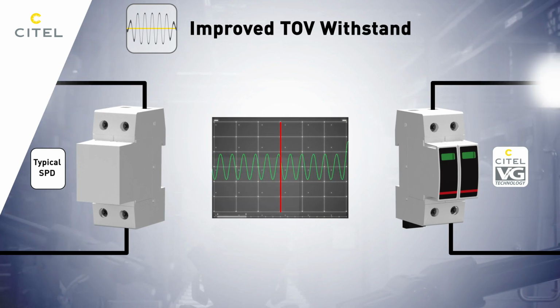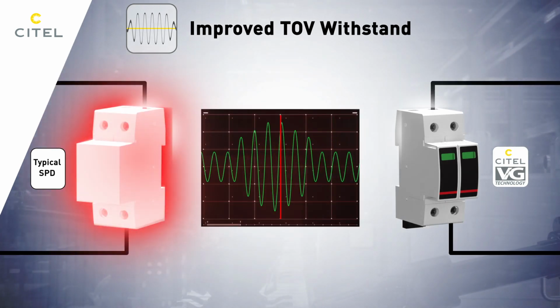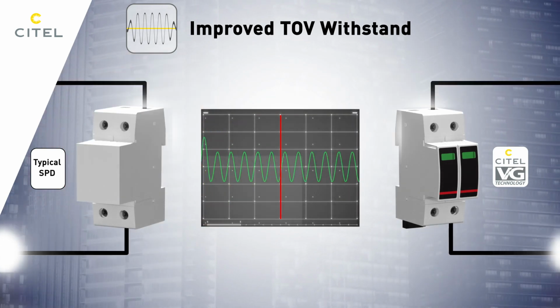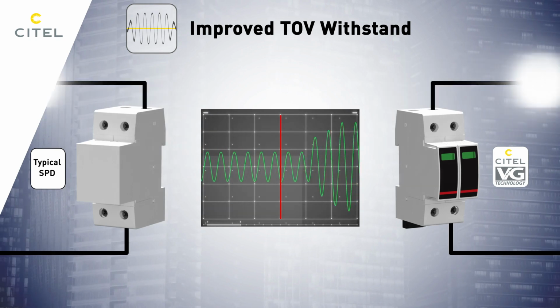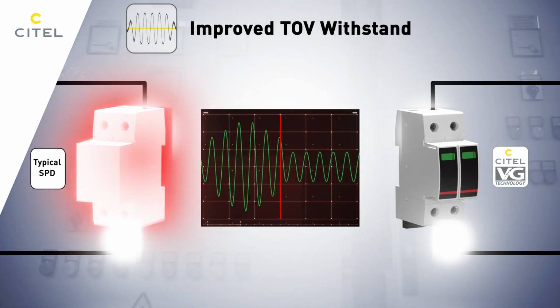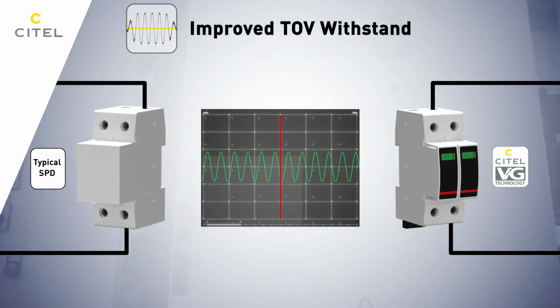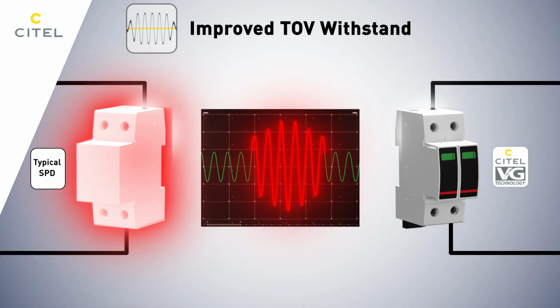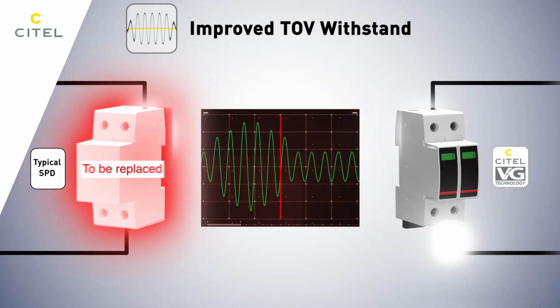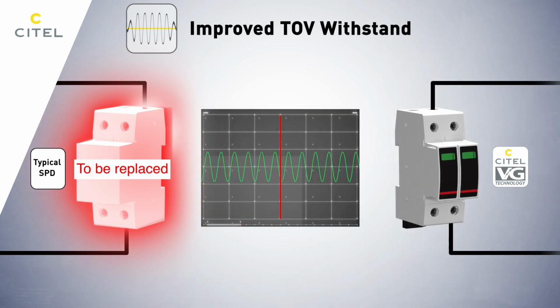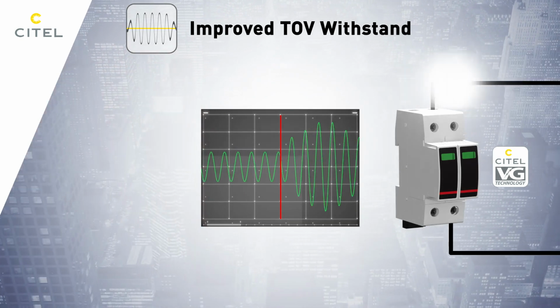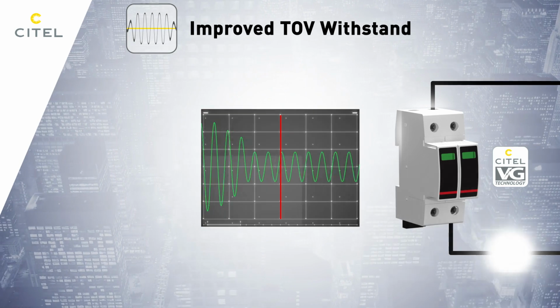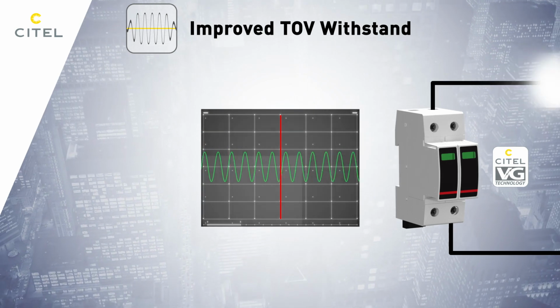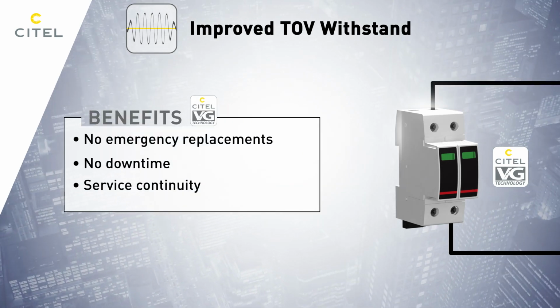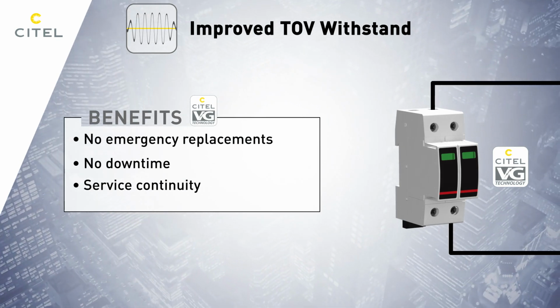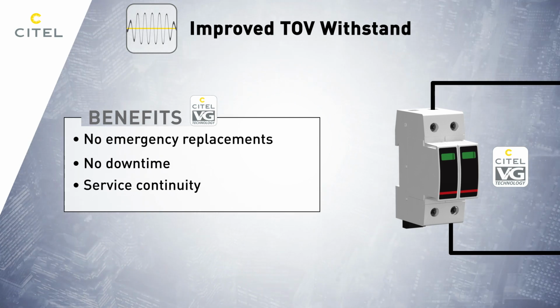Temporary overvoltages, or TOVs, are short-term voltage increases in an electrical system that last from a few milliseconds to several seconds, yet cause serious damage to equipment or premature aging. When exposed to a TOV event, Metal Oxide Varistors, or MOVs, can fail by either disconnecting from the network or degrading their performance. So MOV-based SPDs are typically disconnected from the grid and need to be replaced, which leads to higher maintenance costs and downtime for the system. VG technology can endure these temporary overvoltage spikes and remain fully operational, continuing to provide surge protection without the need for replacement or system downtime. No emergency replacements, no downtime, guaranteed service continuity, ideal for critical installations where every second matters.